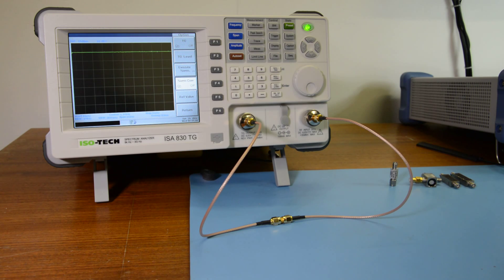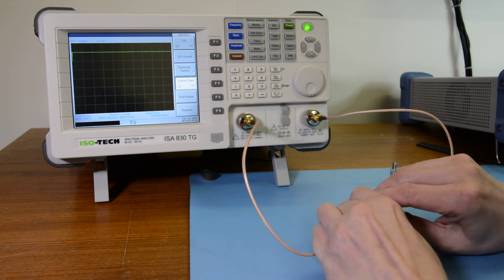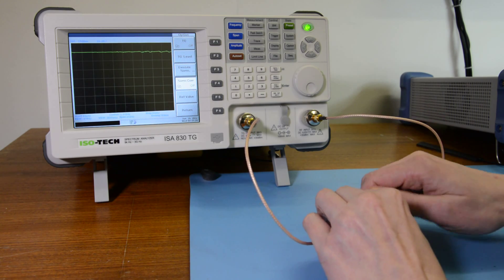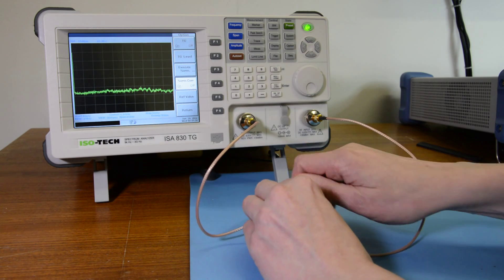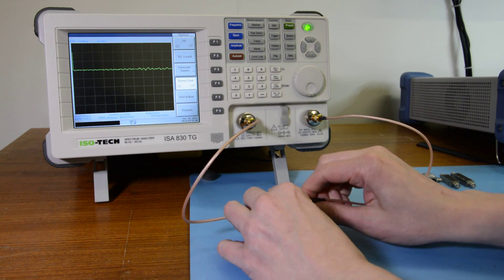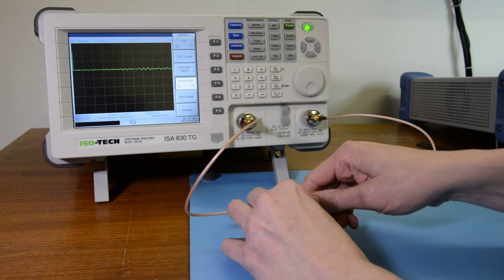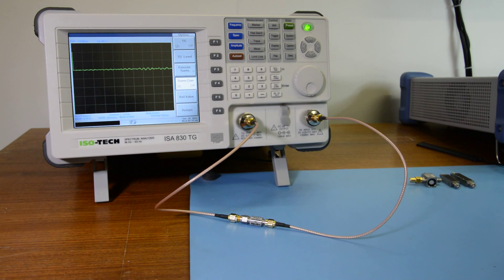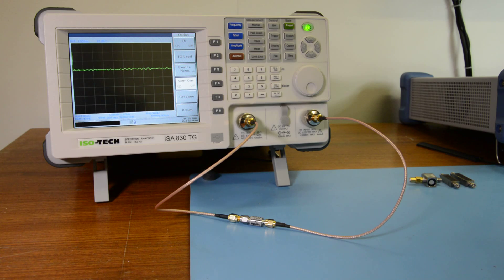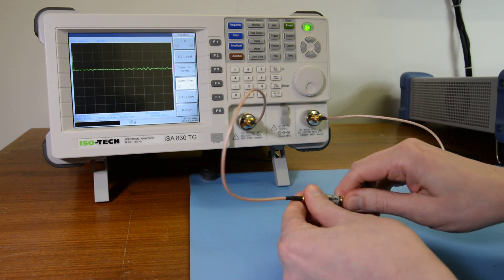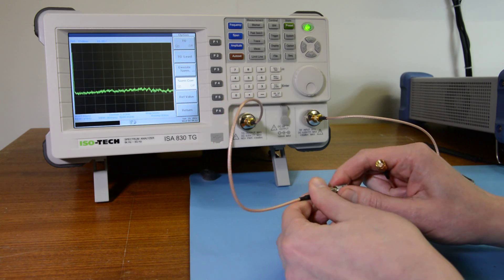Now the first component that we're going to look at is a simple 20 dB attenuator or pad. So we disconnect one end of this cable and leave this join in place and then set the attenuator. We can see that there's been a reduction in two squares which is 20 dB. It's 10 dB per division. So that's just as we would expect. Take the 20 dB attenuator out of line.